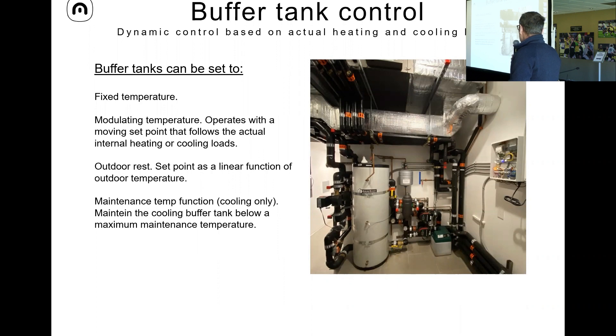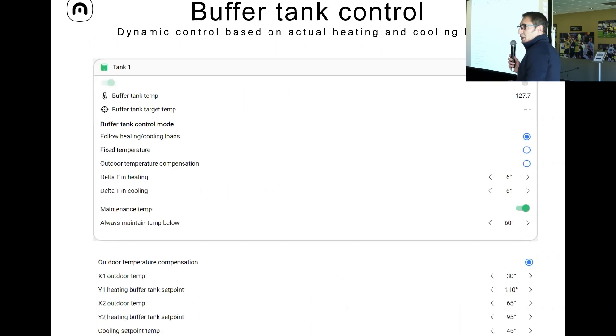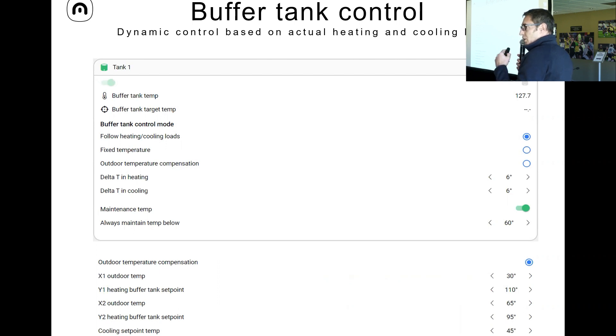There is also a maintenance temperature function — in cooling, if you don't want to stress the heat pump in a hot summer, you can maintain your buffer tank so it never goes above a certain temperature by setting this function. Here is how the control interface looks for the buffer tank. You can see the target temperature, which is the actual temperature we are trying to dictate to the buffer based on the modulation logic.